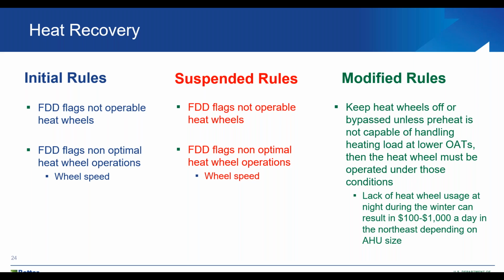Heat recovery. So there are a lot of systems out there with heat recovery, especially, we see a lot of them here in the Northeast, talking more about heat wheels. So they're operated both for heating and cooling. And initial rules for heat recovery are typically based on, is the heat wheel operating? And then, is it operating under optimum conditions? Is it operating at the right outside air temperatures? Is it spinning at the right speed? Is it providing what it's supposed to be effective?